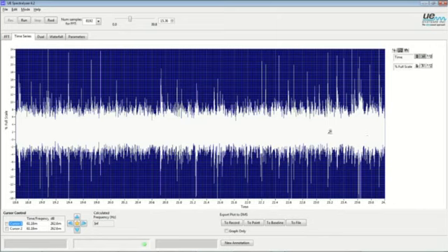Well, we still see the broad band of white noise across the middle, which is to be expected, but now we can see with greater detail these deviations which represent the energy discharges. And we know they vary as far as their amplitude, which tells us the intensity of the discharge, as I mentioned before, is changing or varying. So some discharges are higher intensity here than others down here.